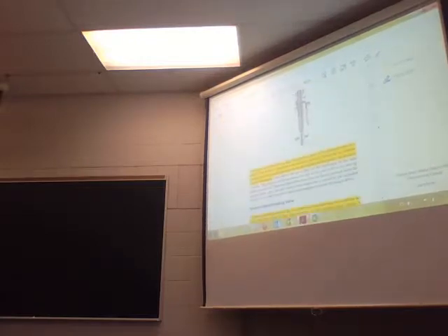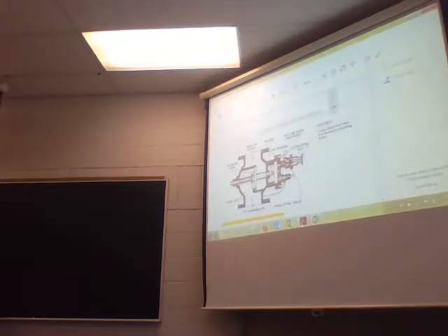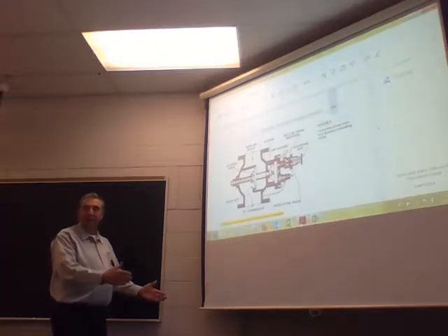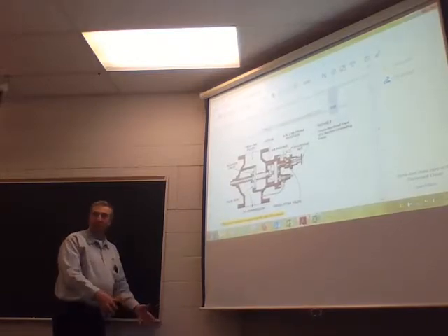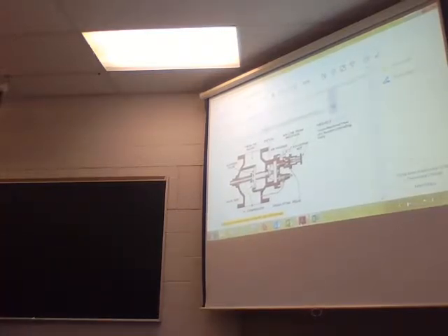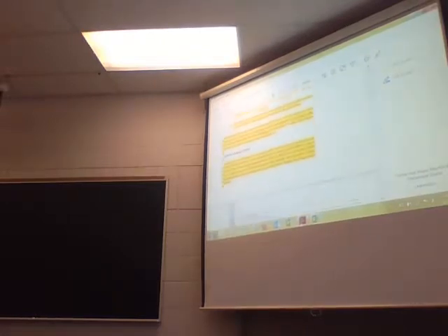If I have problems with the suction line unloader valve, you can see that it's either screwed or flanged, connected in the line. If my valve has a problem, it's no big deal because it's over here, in between the filter and the compressor. All right? Got those two? Say yes. Yes. Good. Only say yes though if you actually mean it.